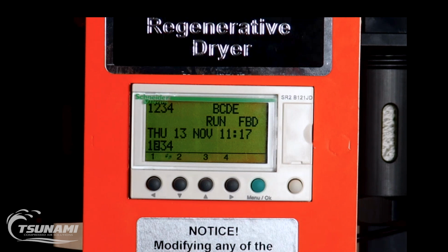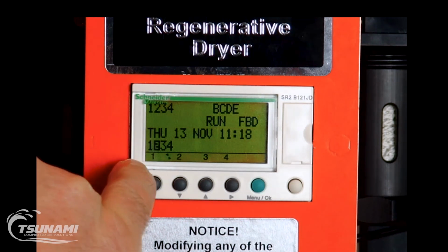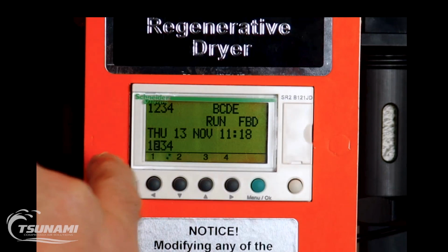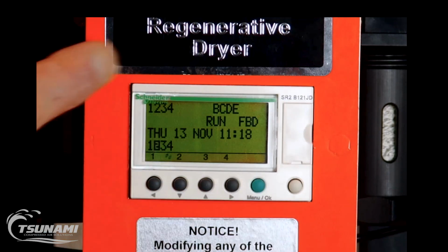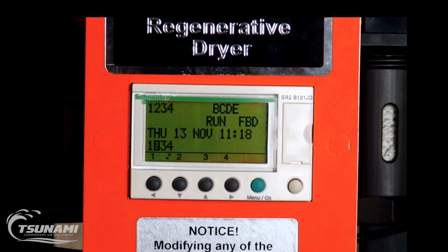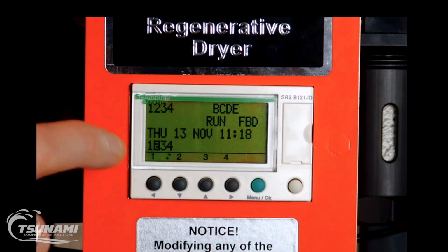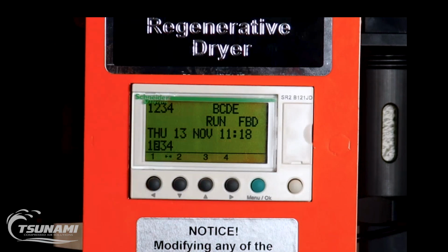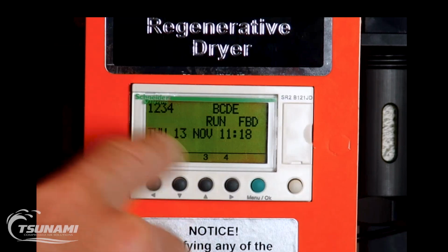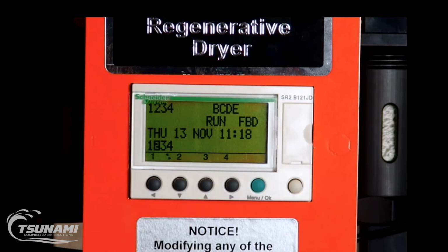And if you're ever troubleshooting with us, we're going to be asking where are the signals at, things like that. The very low numbers, these are determining digital and analog inputs. So the top numbers are going to be digital inputs, and the bottom numbers will be analog inputs. The PLC says it's in a run mode, and we also know that it's in a run mode because you see those little spinny dots down below. That tells us that it is in a program and it is cycling and reading the program.